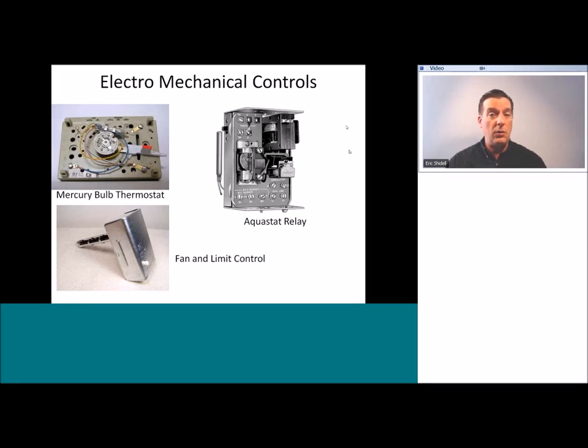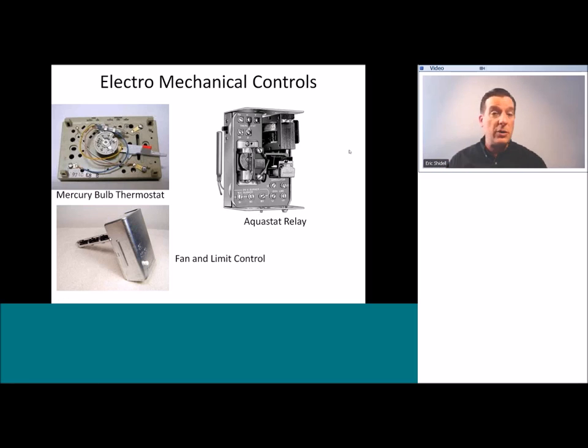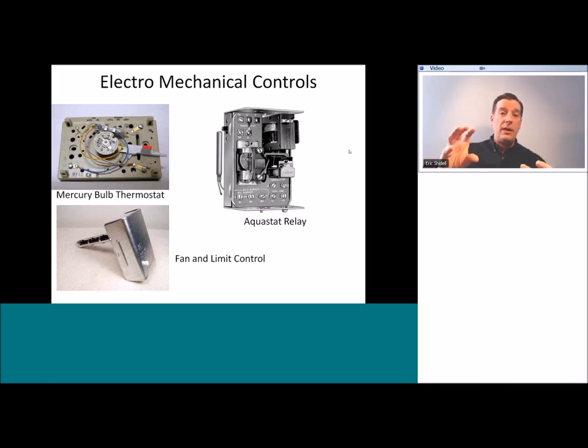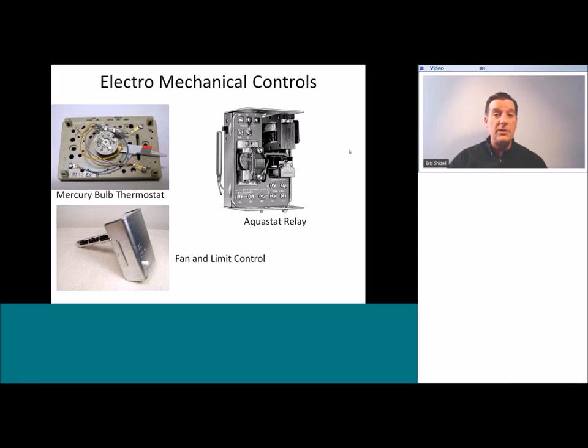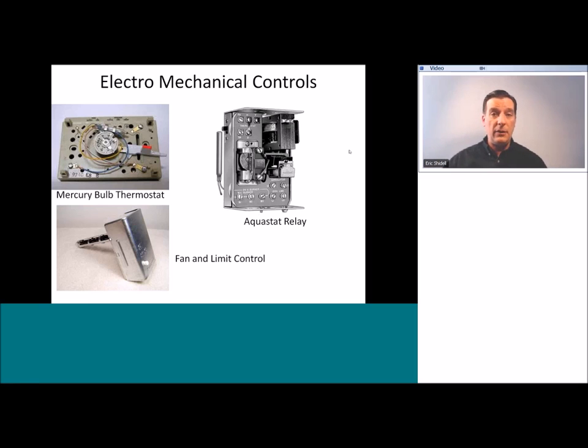The fan and limit control from old forced air furnaces has a temperature sensitive element that moves in response to temperature inside the furnace. As the furnace warms up, it moves and trips a switch to turn on the fan. At the end of a heat cycle, it moves back as things cool off to turn the fan off. It also has a dual purpose: if the temperature gets way too high, it trips a switch to shut off the burners so things don't overheat. Once again, something physically moving operates a switch which controls the final outcome.